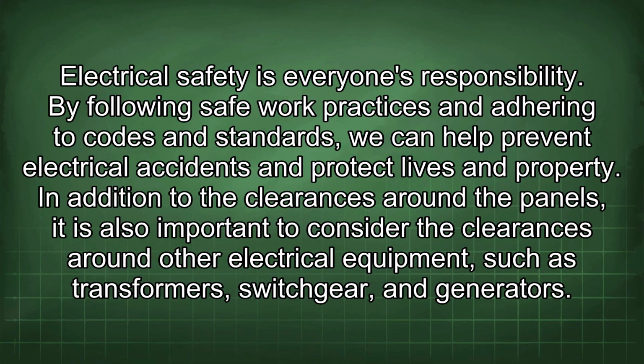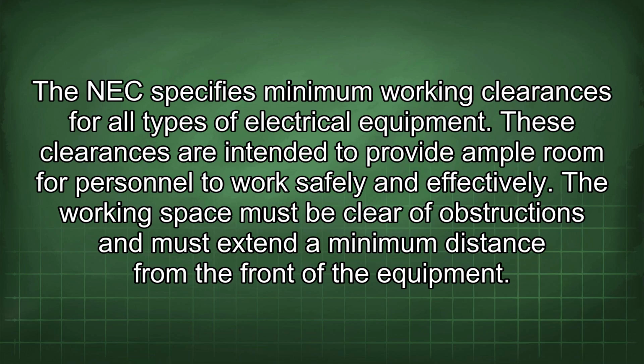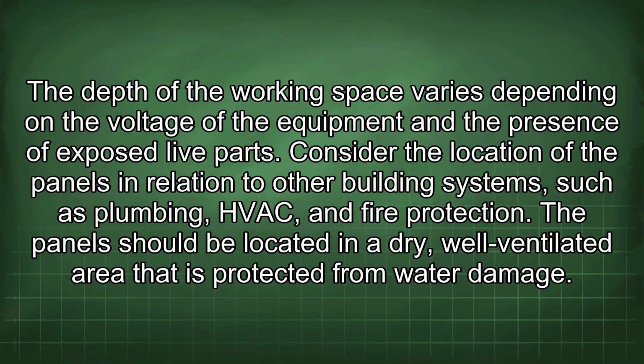In addition to the clearances around the panels, it is also important to consider the clearances around other electrical equipment, such as transformers, switchgear, and generators. The NEC specifies minimum working clearances for all types of electrical equipment. These clearances are intended to provide ample room for personnel to work safely and effectively. The working space must be clear of obstructions and must extend a minimum distance from the front of the equipment.